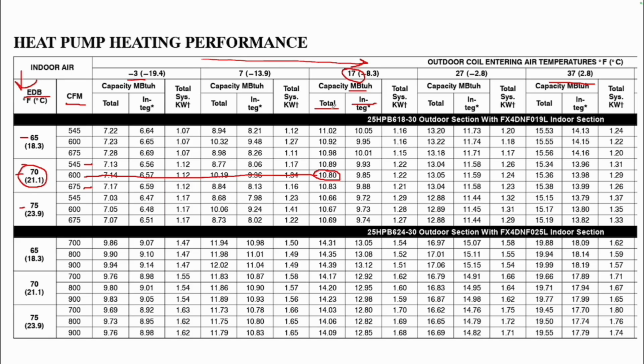here. And so you can see how this chart works, right? So we locate our outdoor temperature, we locate our indoor dry bulb and the CFM, and then we're able to plot this out. Now, here we go from 17, then it goes up to 27. So that's a 10-degree gap. But the difference is only about 3,000 BTUs in between that 10 degrees. And so I can fairly easily interpolate in between those two, depending on if I'm in the middle of that, or maybe I'm at 23 degrees. It's not hard to actually take the amount of degrees in between these two columns and the amount of BTUs between them and come up with an easy way to determine about what those BTUs should be.